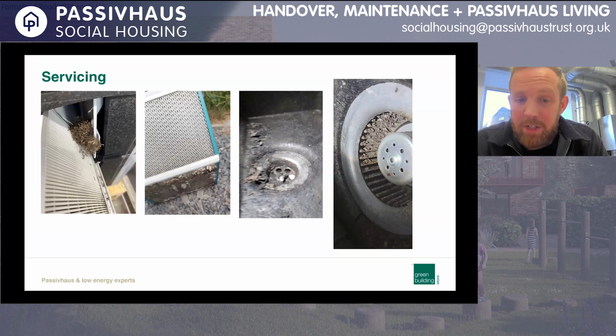Next, we've got a heat exchanger, which has got considerable mold growth on it. These need changing. It's nice to check them every year, but cleaning every 4 years is fine. This system had been turned off. This one was in a social housing scheme. They'd turned it off because of the noise, and therefore mold buildup had occurred. We couldn't actually clean that one sufficiently, so it resulted in a new heat exchanger.